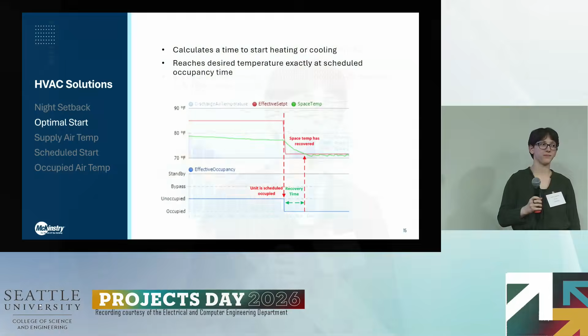For optimal start, with our temperate climate here, we tested reducing this allotted time for the building to heat up. This reduced the energy usage, so we chased this until we saw a point of diminishing returns. Then we backed it off slightly, because this is a very simplified model, and when it runs into reality, sometimes those systems take a little longer to get the building to temperature. And so we backed it off to 0.3 hours, and this resulted in an 11,000 kilowatt hour reduction in energy usage, which is about 5.2% energy savings.